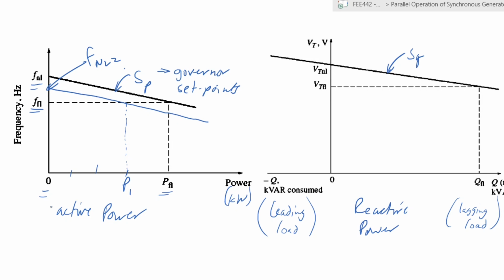So at zero, instead of running at, say, 1400 RPM, you could run it at 1300 or something like that. And by dropping it like that, you drop the entire line to a lower level such that you can supply your P1 at the frequency that you desire. This is what we call governor set point adjustment. Okay. Normally, when it is running, you would not touch the governor set points. These are predetermined. However, if you want to now adjust, you can do so.